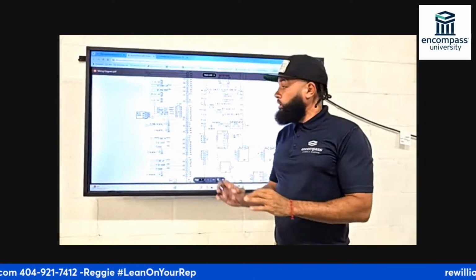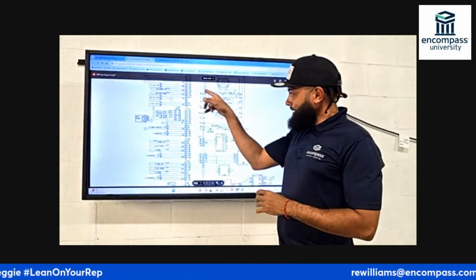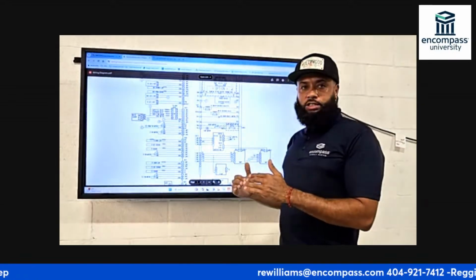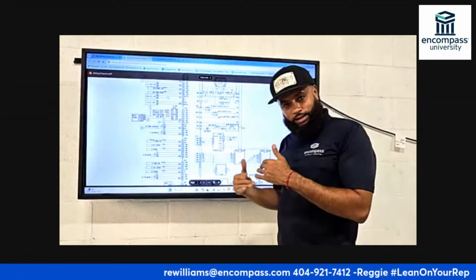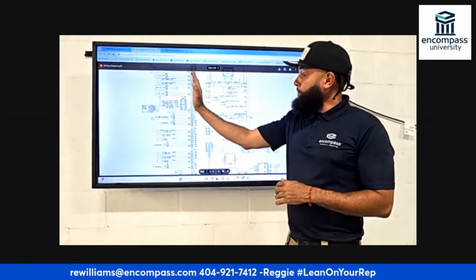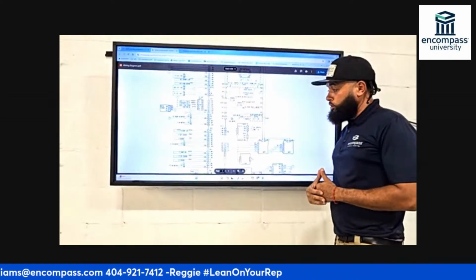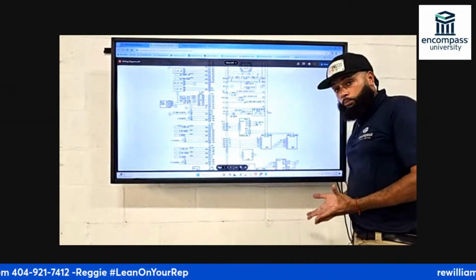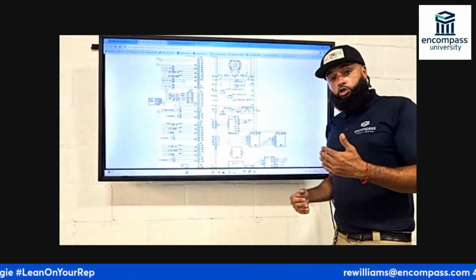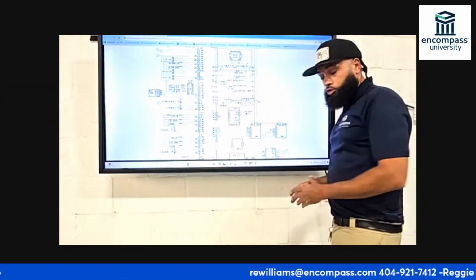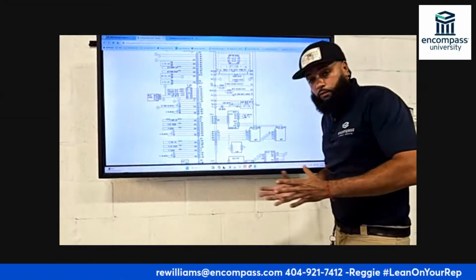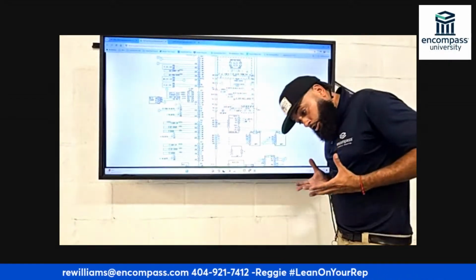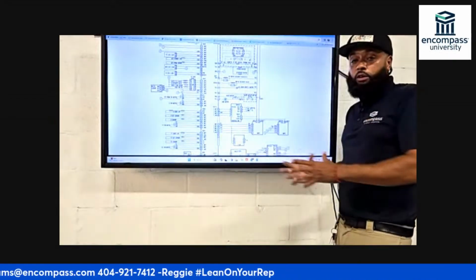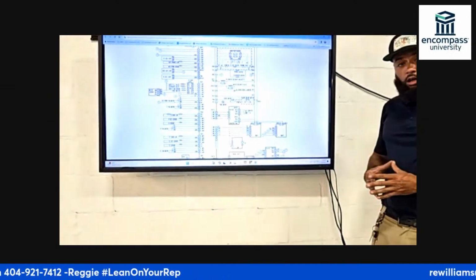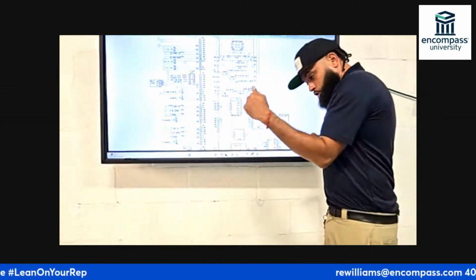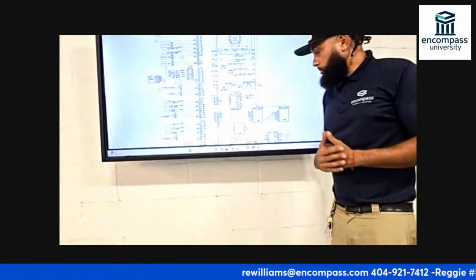At that point, when the fridge is in forced defrost, you want to take those live tests and make sure the board is sending the output voltage. But for the compressor, make sure it's on FF1, and make sure the board is sending the right output voltage to the inverter, and the inverter is sending the right output voltage to the compressor. So you've got one board speaking to another board, then speaking to the compressor.